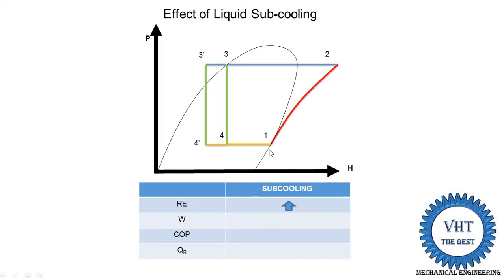The second point is work done. There is no change in the work done, which is H2 minus H1. In the simple case and when we install subcooling, it is the same — no change in work done. What is the change in COP? The COP of the system is increased because its definition is refrigerating effect divided by work done. Since refrigerating effect is increased and work done is the same, the COP of the system is increased.